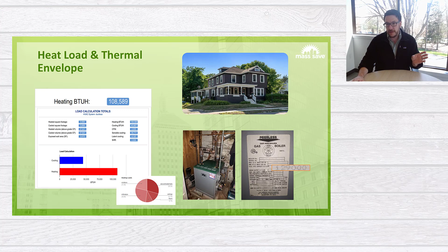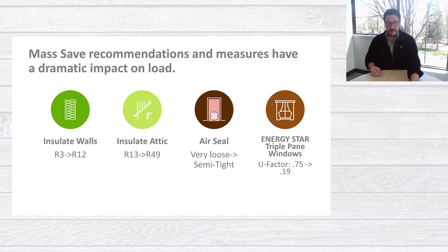For this home, even though it was listed at 108,000 BTUs per hour, you do not need to design a heat pump system for 108,000 BTUs per hour. First, you should always insulate and air seal. So instead of having uninsulated walls, packing those walls full of insulation. Instead of only having 3 inches of insulation in the attic, getting it up to code minimum. Air sealing everything that's possible. So around the rim joists, up in the attic, the knee walls, the slopes, really just making sure that the home is no longer having catastrophic air leakage. And then also upgrading the windows. The home had single pane with storms, upgrading them to an Energy Star window, or even better, a triple pane window.